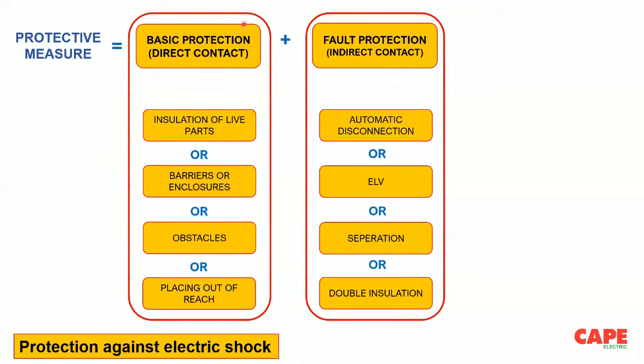So basically, all these techniques are applicable for certain applications. Sometimes we may use one basic protective measure and one fault protective measure. Generally, the measure we use for basic protection is insulation of live parts, or barrier or enclosure, inside a low voltage consumer premise, and for fault protection, automatic disconnection or extra low voltage. These two are made. Of course, separation is also made in some cases.